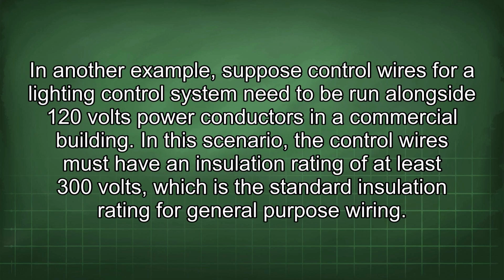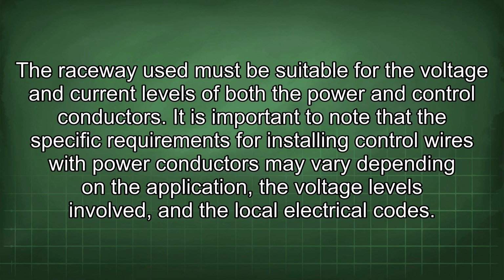In another example, suppose control wires for a lighting control system need to be run alongside 120 volts power conductors in a commercial building. In this scenario, the control wires must have an insulation rating of at least 300 volts, which is the standard insulation rating for general purpose wiring. The raceway used must be suitable for the voltage and current levels of both the power and control conductors.